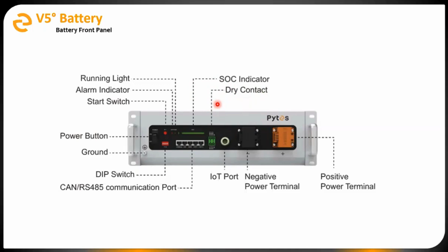Then the battery-to-battery communication ports are the link ports, which allow each battery in a specific group to talk to each other and share info. This one right here in the middle is one of the new additions we've made on the V5 — an IoT port, specifically used for that Wi-Fi monitoring dongle I mentioned. Lastly, we've incorporated a dry contact relay into this product, which can be used for ESS emergency shutoff if that's required for any installation.